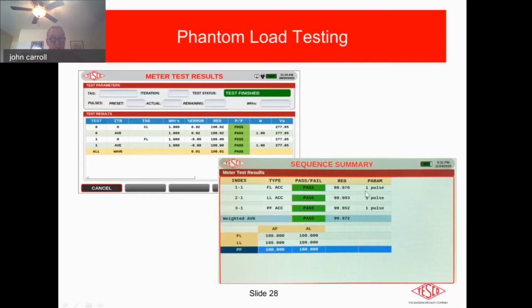And that was done with 1 pulse. So it's pretty impressive with 1 pulse. Not always easy to do it with 1 pulse. Sometimes it might take a little longer, but if you get the accuracy you need with 1, you don't really need to do 10. So it's a question of doing a very quick test on that.